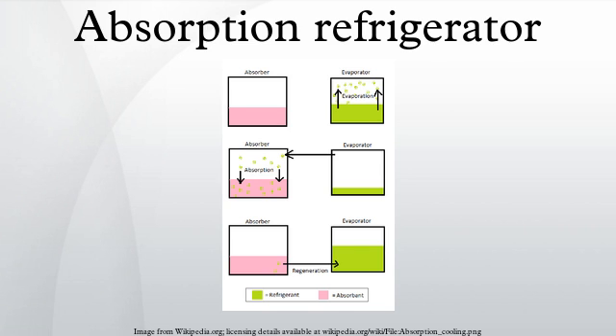The next three steps exist to separate the gaseous ammonia and the hydrogen. The ammonia and hydrogen solution flows through a pipe from the evaporator into the absorber. In the absorber, the solution of gas flows into a solution of ammonia and water. The ammonia dissolves in the water allowing the gaseous hydrogen to collect at the top of the absorber, while the ammonia and water solution remains at the bottom.